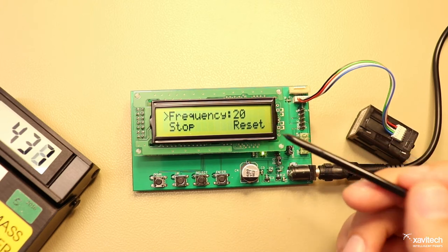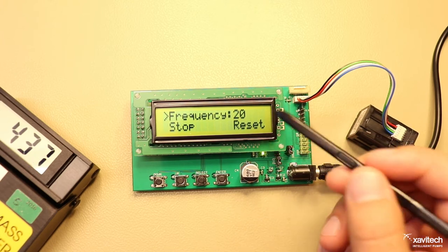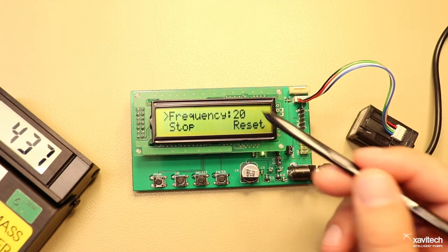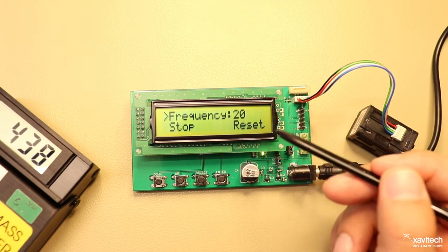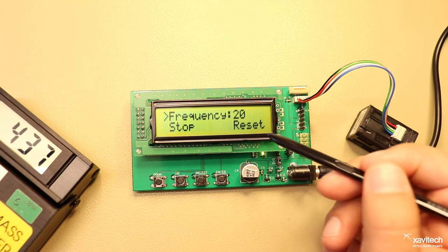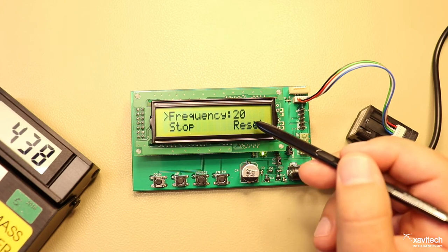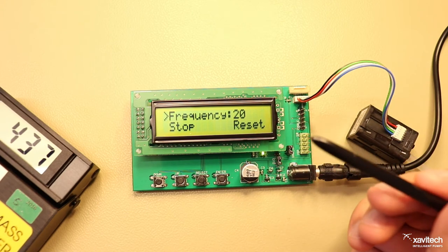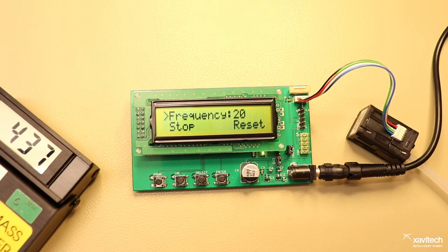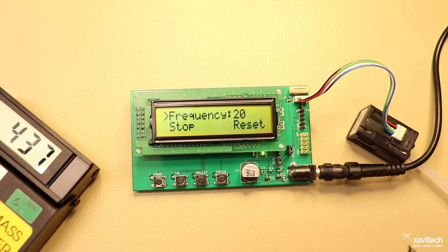We do not recommend that the value is set lower than the original, in this case 20. If set lower the pump will run faster and in this case we cannot guarantee that the pump functions properly.